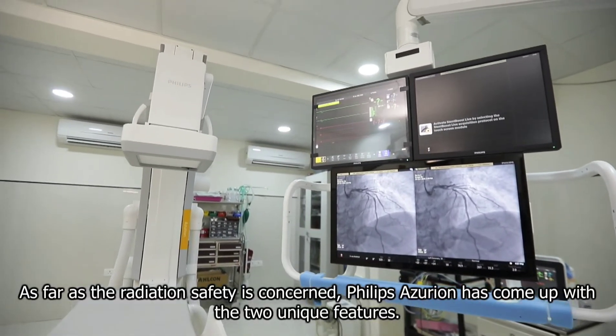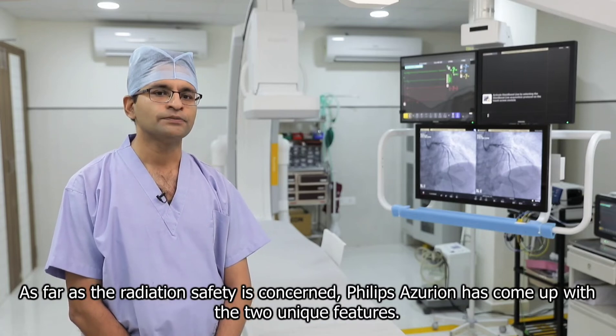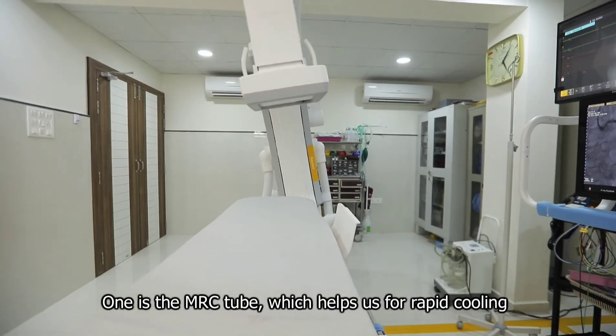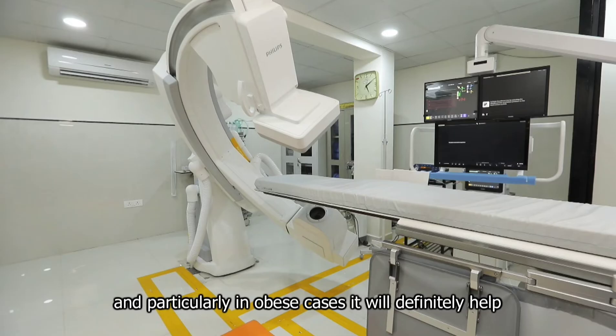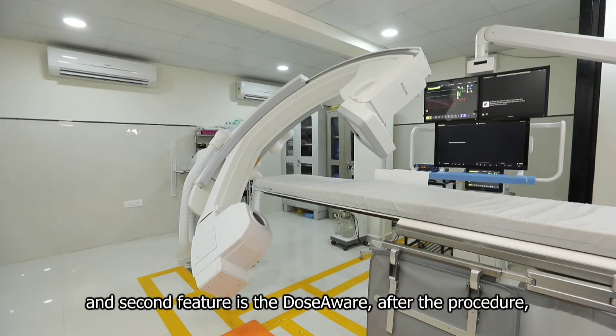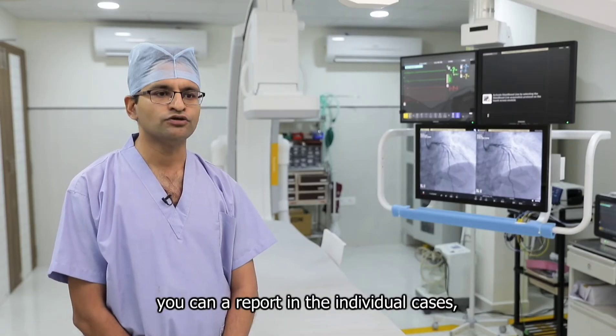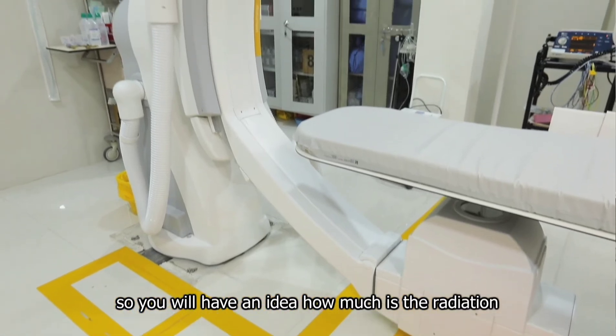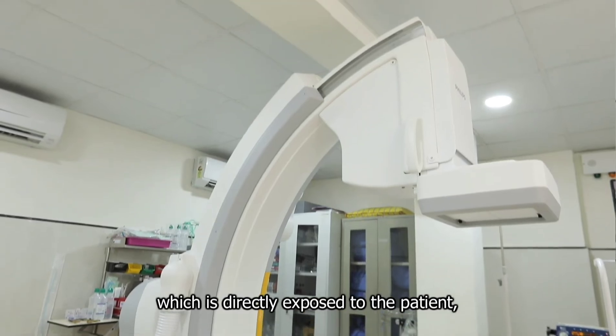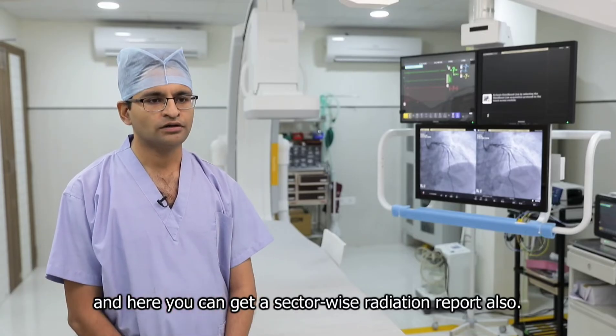As far as radiation safety is concerned, Philips Azurion has come up with two unique features. One is the MRC tube, which helps with rapid cooling — particularly in obese cases, it will definitely help deliver less radiation to the patient. The second feature is DoseAware. After the procedure, you can get a report for individual cases, giving you an idea of how much radiation was directly exposed to the patient, and you can also get a sector-wise radiation report.